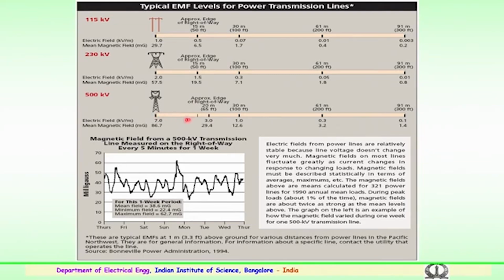As the distance from the tower increases, the values of the electric field and the magnetic field get reduced. Initially, 7 kV per meter is the electric field and 86.7 milligauss is the magnetic field near the high voltage tower. It reduces as you go farther away from the tower, say 91 meters, approximately 300 feet, where the electric field reduces to 0.1 kV per meter and the magnetic field reduces to 1.4 milligauss. So, this is information for the electric and magnetic fields pertaining to the higher transmission levels.